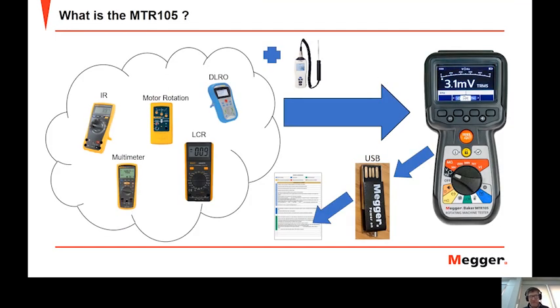So what is the MTR105 and what can it offer you? In simple terms, it's a multifunctional handheld test unit that replaces several single-function units. By incorporating a suite of IR tests, a voltmeter, a motor rotation test, continuity tests, a digital low ohms resistance test, or DLRO, an LCR meter, and also a temperature sensor into one small handheld unit, we offer the customer numerous benefits. And we can even export the data that we take from the MTR into our PowerDB Lite software, which is free of charge software to allow you to create professional reports.